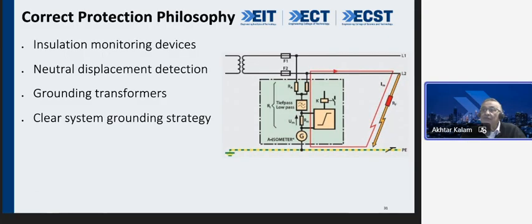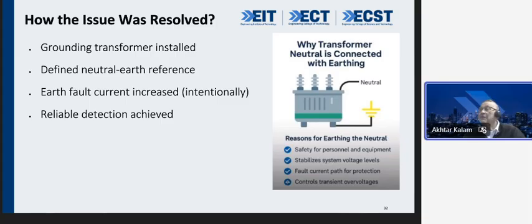So, how was the issue resolved? Something someone might ask. Install the grounding transformer. Define your neutral earth reference. Increase the earth fault current intentionally. Have reliable detection. And this is where you will find that having these earthing transformers, which is the grounding transformer that I'm talking about, addresses the non-detection of ground faults, especially in underground, ungrounded systems, or what I call high impedance grounded electrical faults, such as a delta connected network. So if you have that, you can solve this problem.